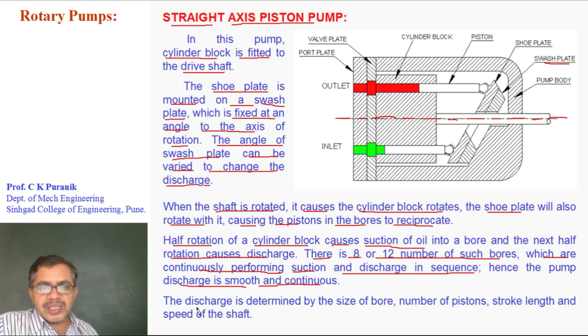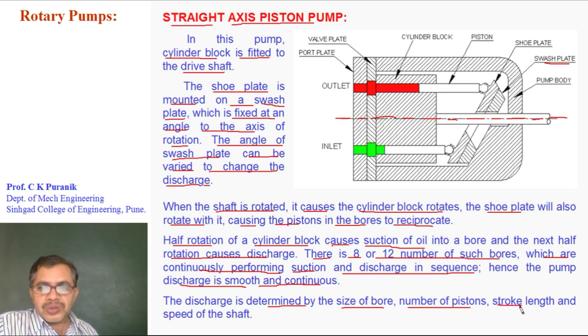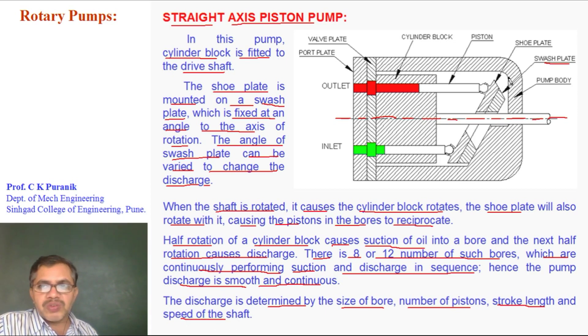The discharge is determined by the size of the bore, number of pistons, stroke length, and speed of the shaft. Stroke length refers to the angle of the swash plate, and we can change the stroke length by changing the angle of the swash plate.